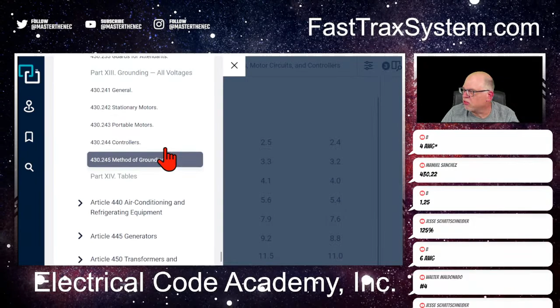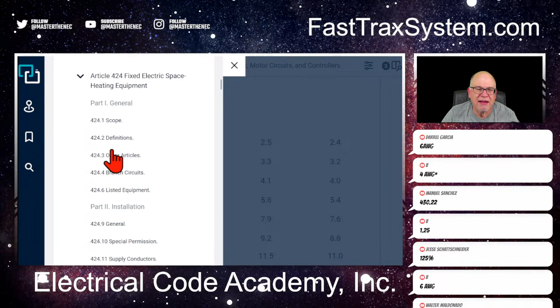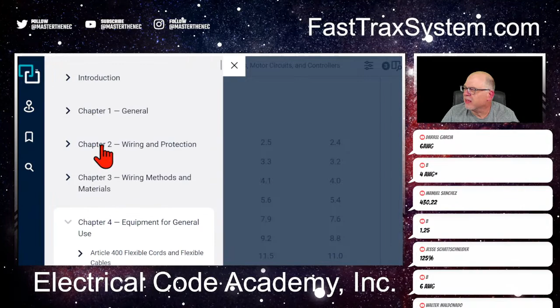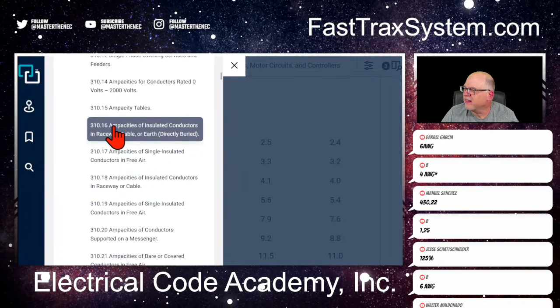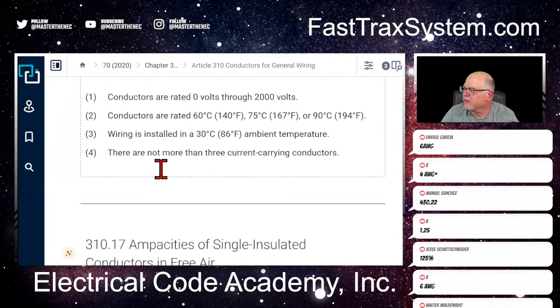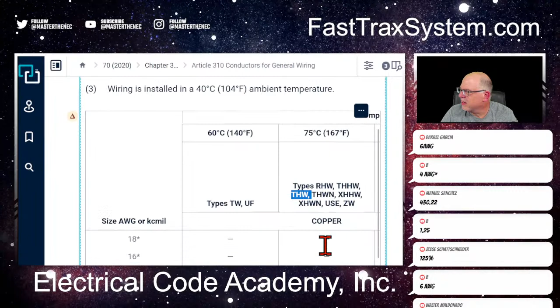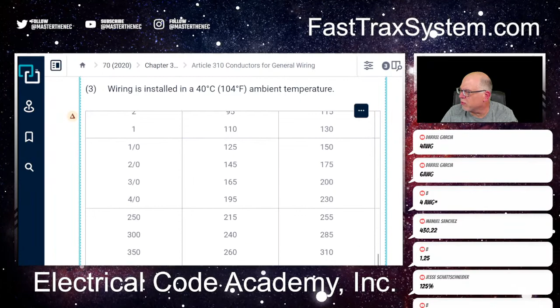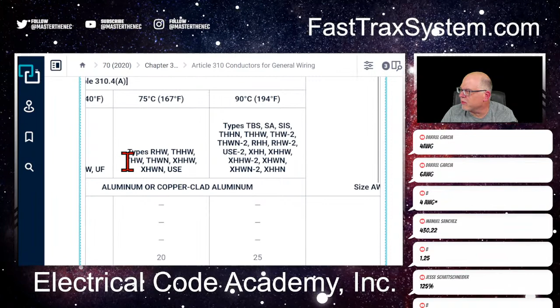So now I'll go to 310.16. That's our ampacity table. If you're in the 2017 code, it's 310.15(B)(16). I'll be glad when I don't have to say that ever again. Remember, we're doing aluminum. Here's the table, and here's THW right here. But this is the copper side, so we have to go over to the aluminum side. All right, we're over here at the aluminum side, so here's the THW under the 75.